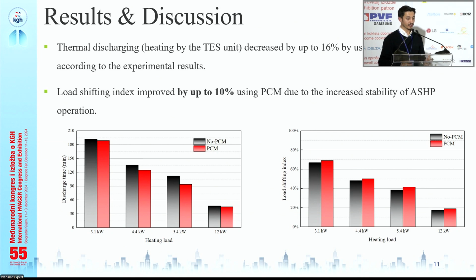However, the load shifting index is improved, although the heating time is decreased. The load shifting index is improved by up to 10% using PCM. This is also attributed to this more stable working of the air source heat pump.